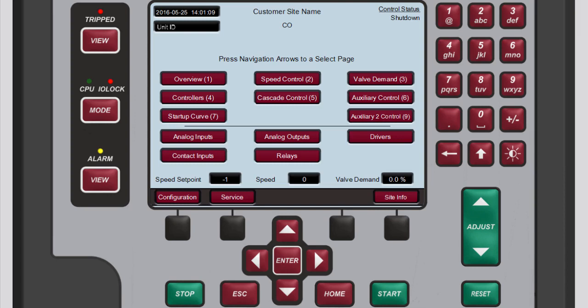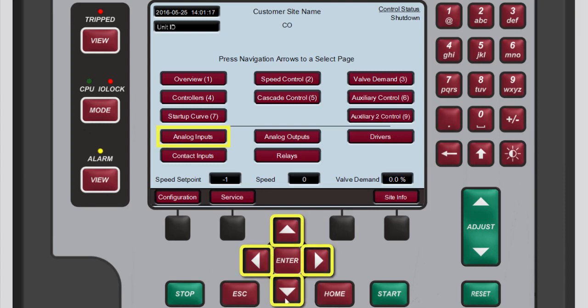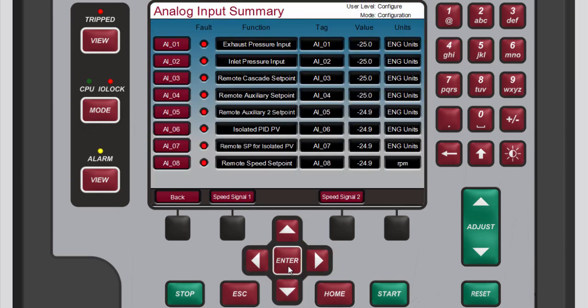To run the open wire test, you need to access the analog input summary screen. To get there from the home screen, use the navigation cross keys to highlight Analog Inputs, and then press Enter. On the analog input summary screen, press the black function key below Speed Signal 1. If you configured the controller for both speed signals, the Speed Signal 2 button will display as well.